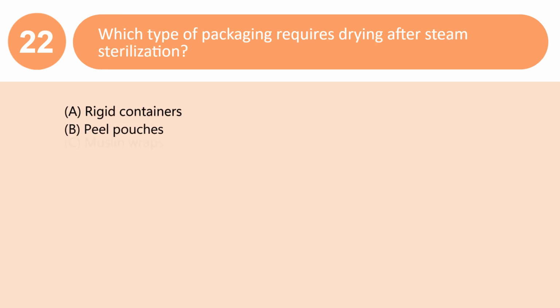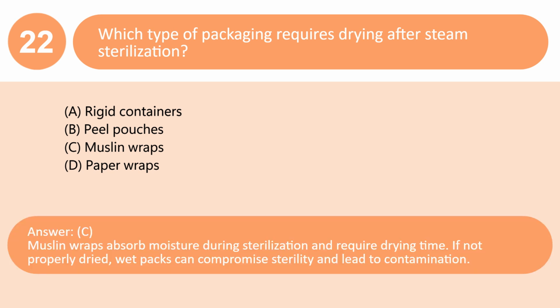Which type of packaging requires drying after steam sterilization? A. Rigid containers. B. Peel pouches. C. Muslin wraps. D. Paper wraps. Answer: C. Muslin wraps absorb moisture during sterilization and require drying time. If not properly dried, wet packs can compromise sterility and lead to contamination.